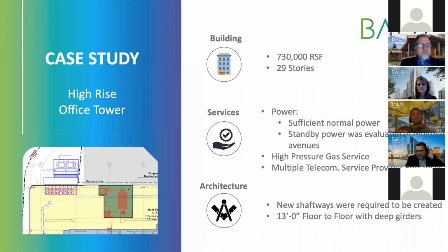Here we're looking at a floor-to-floor of roughly 13 feet, and we had to deal with a couple of deep girders in some areas. The way we handled that was looking at our room layouts and working with the architect to move equipment around, such as a fume hood, to avoid these deep girders. A typical fume hood wants a nice long sweeping elbow into it, which helps promote good airflow into the face of the fume hood in the room. So it's important to take heed of where that equipment needs to be and the type of duct configuration it would require. Okay, next slide.